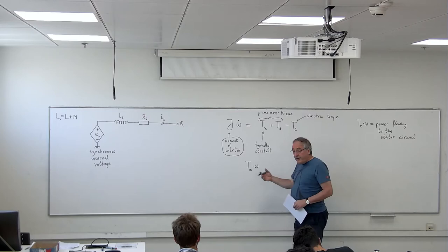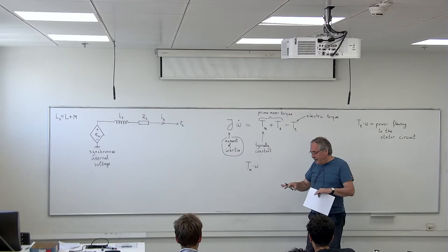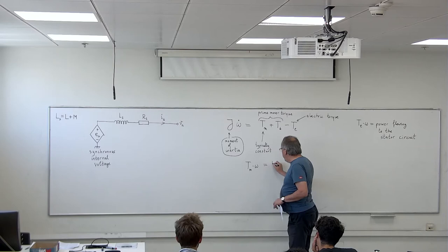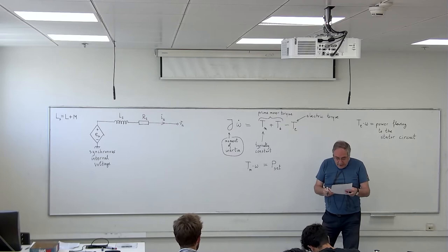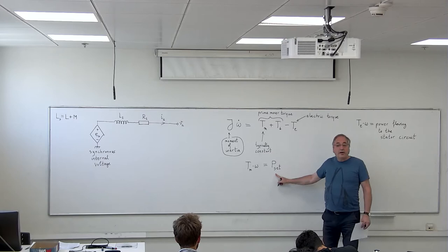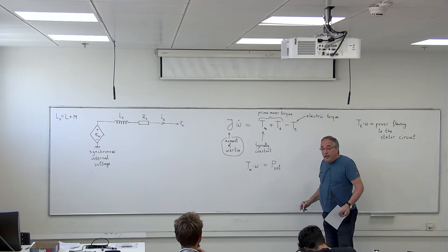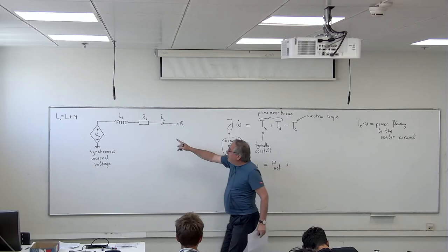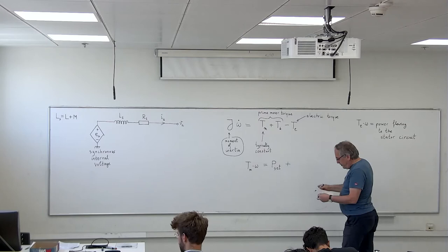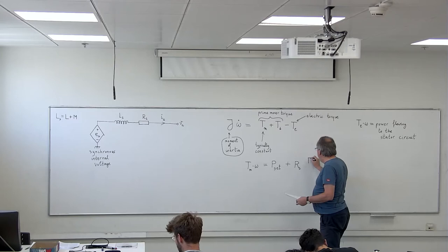Now this power will be divided in an unequal way between the power that actually flows to the grid, and for that you have a certain desired value, the set value of the power that the operator of the power station wants to send to the grid. And then you have to add to this also the power that will be lost on this resistor. So the power lost on this resistor has a relatively more complicated expression.